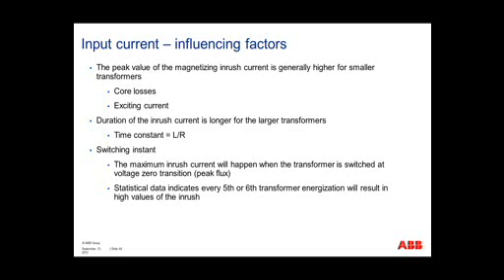So, influencing factors on how much inrush current you'll have. Typically, for the smaller transformers, you'll have a higher peak inrush current, but it will typically last for a shorter amount of time. The larger the transformer is, you'll have a smaller amount of inrush. However, that inrush time is a lot longer. Also considered is when you switch the transformer on from the system and start bringing it online, when you start saturating the transformer. When you bring the transformer online at the voltage 0 crossing, that's when you're going to experience your peak inrush. If you have current going into the transformer, no current leaving the transformer, the differential sees that as a fault condition and trips. So we need to have a way to account for this inrush condition.